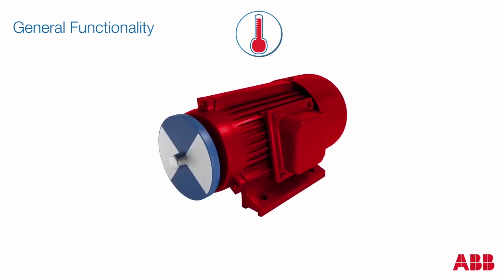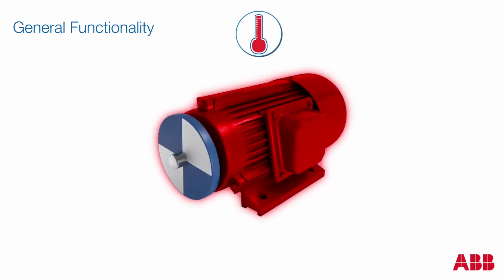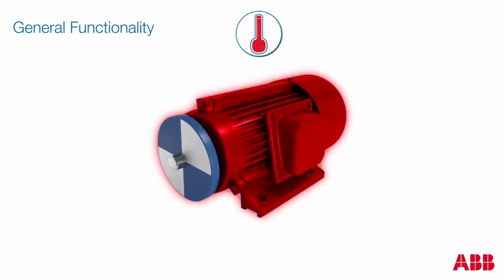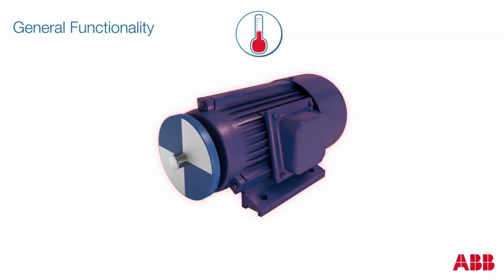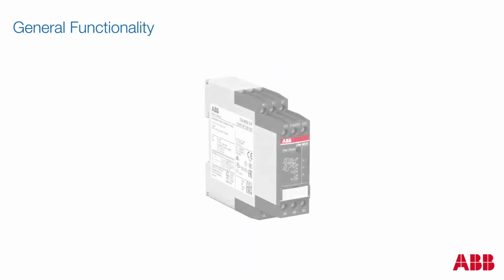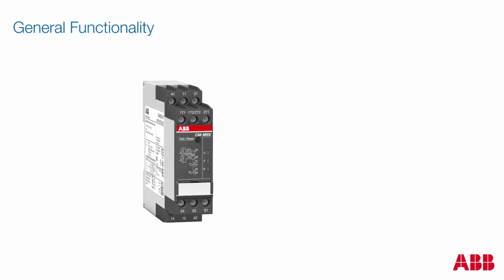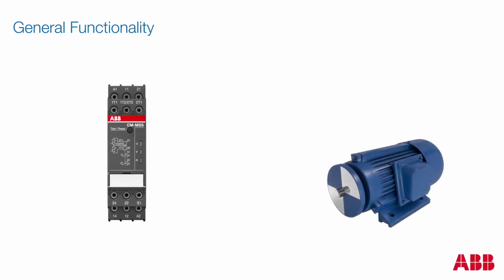These can be abrasion, which is caused by increased stress of the moving parts, or electrical failures caused by overtemperature, which leads to an insulation breakdown of the windings. The direct measuring principle is carried out by a combination of the thermistor motor protection relay and 3 PTC sensors, which are installed directly in the motor by the manufacturer. Those 3 PTC sensors are placed directly at the thermal hotspots, the motor windings.